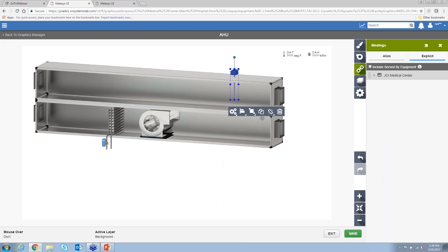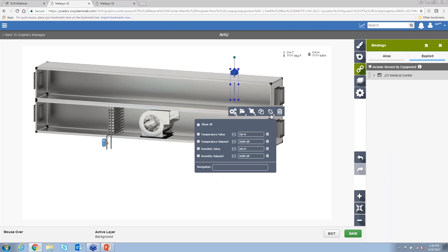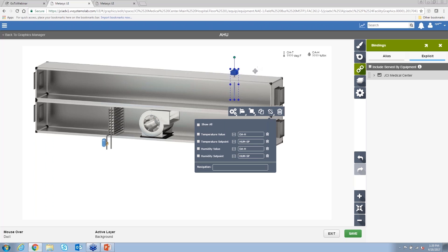There's another feature with our binding. So if you do have a standard naming convention on site that's used, you match these names up and you don't have to do any binding anymore. This comes in for free basically. So if the name matches, the binding comes in and you're done. And it really makes it simple to build these graphics.